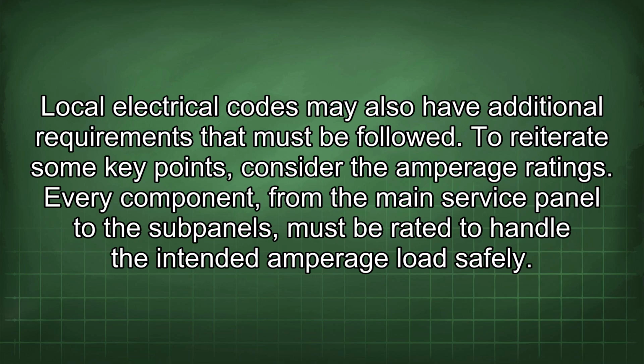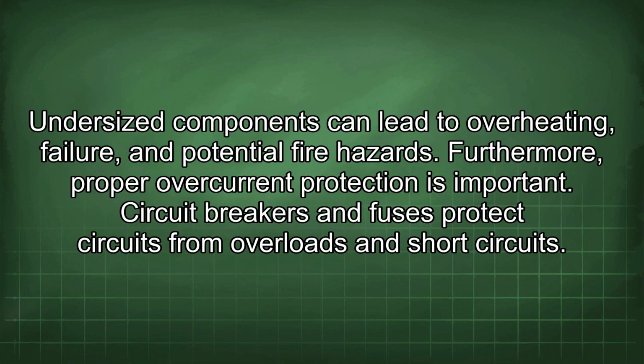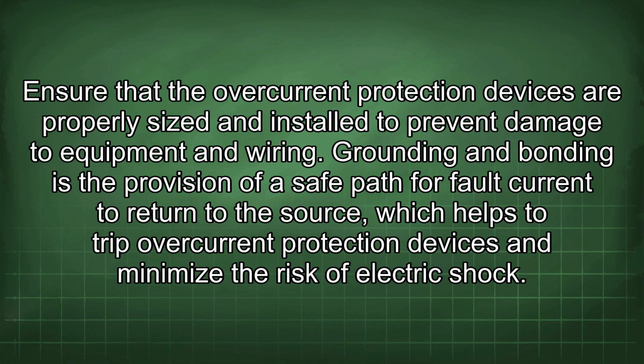To reiterate some key points, consider the amperage ratings. Every component, from the main service panel to the subpanels, must be rated to handle the intended amperage load safely. Undersized components can lead to overheating, failure, and potential fire hazards. Furthermore, proper overcurrent protection is important. Circuit breakers and fuses protect circuits from overloads and short circuits. Ensure that the overcurrent protection devices are properly sized and installed to prevent damage to equipment and wiring.